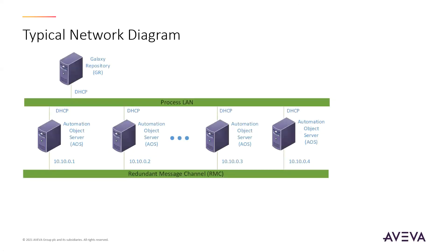In this simplified network diagram illustrating the redundant message channel concept, we have four platforms each connected to a process LAN. That process LAN typically has IP addresses assigned by a DHCP server. The redundant message channel uses a separate set of NICs with manually configured IP addresses. The IP address assigned to the platform tells it which NIC card should be used to find the RMC network — typically using a 10.10.0 IP address naming scheme on the RMC.